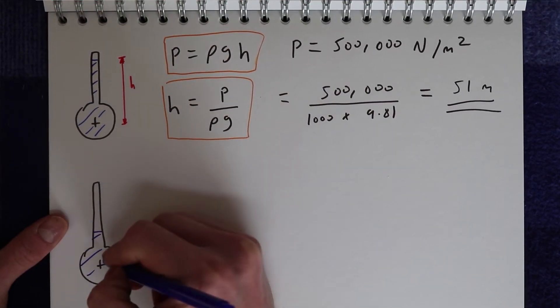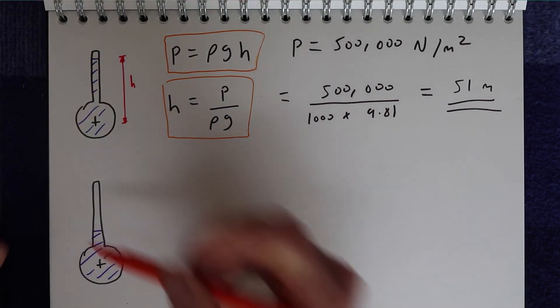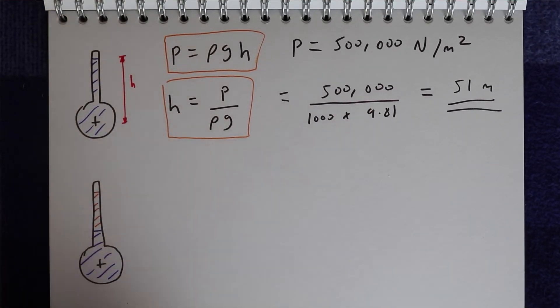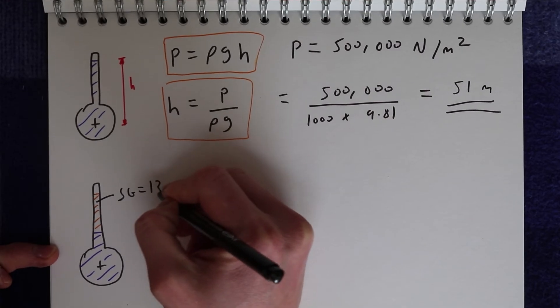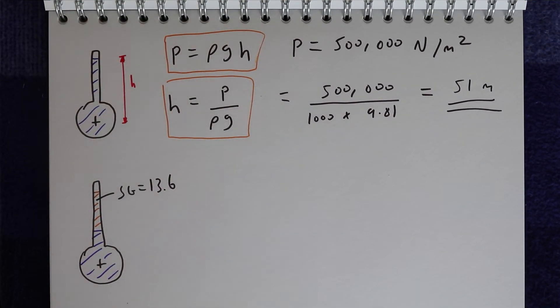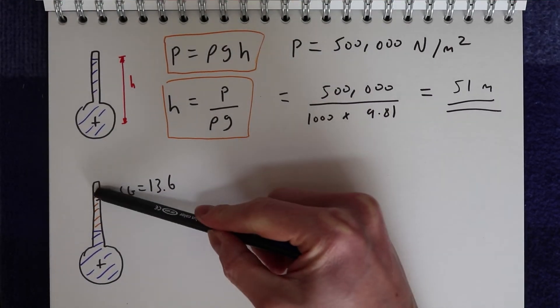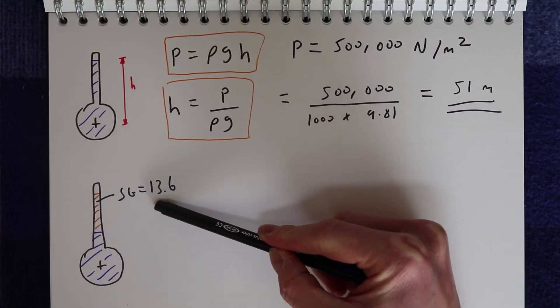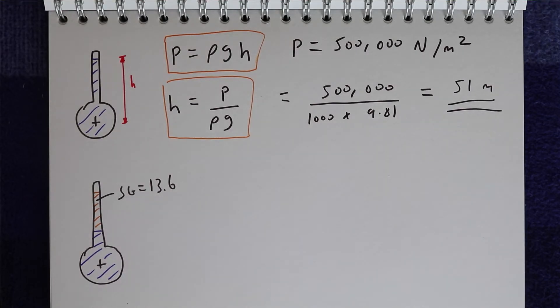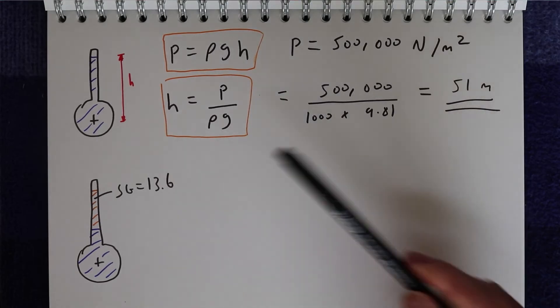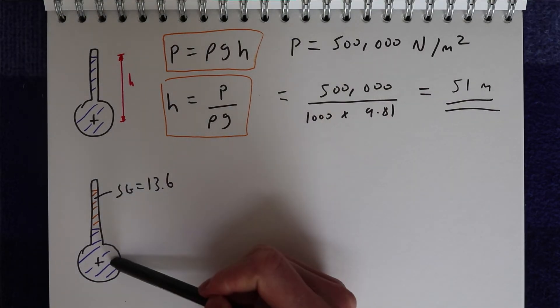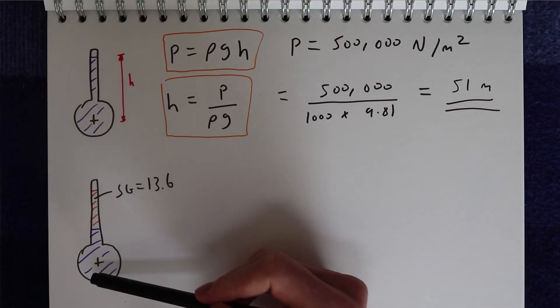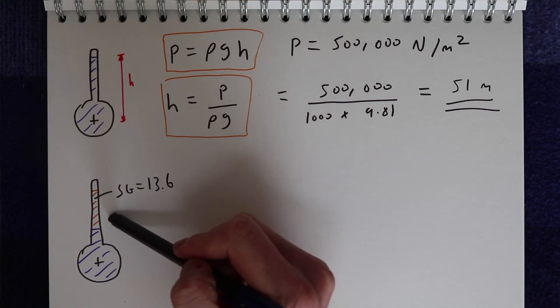So if we replace some of that water with a fluid with a much higher density, the higher that density the lower our H is going to be. So if we replace it with something like mercury that has a specific gravity of 13.6, which means it's 13.6 times more dense than water, the height of that fluid in our gauge is going to be 13.6 times less than if it was just water. So we're going from a piezometer that's maybe 51 metres high to something just a few metres high. However, if we turn off the pipe and the pressure goes to zero, the mercury will just fall down into the pipe and disappear with the water, so every time we turn the system off we lose our gauge fluid.